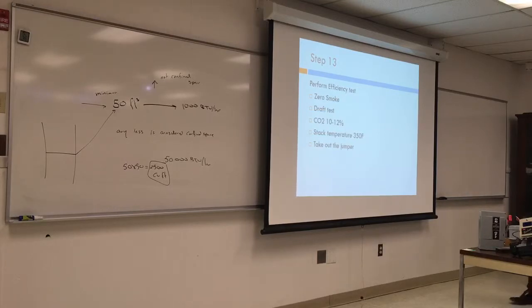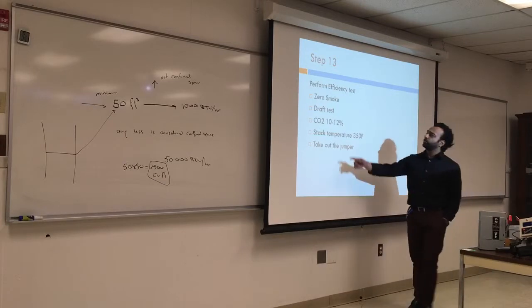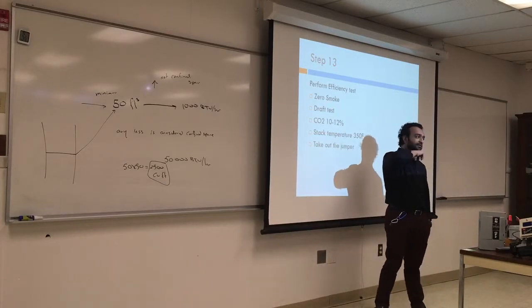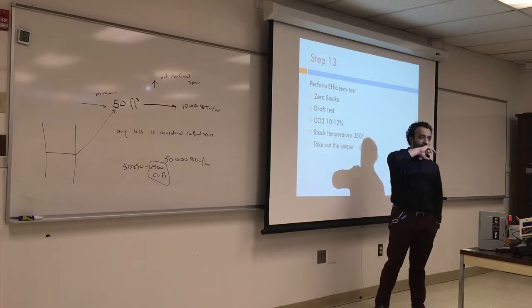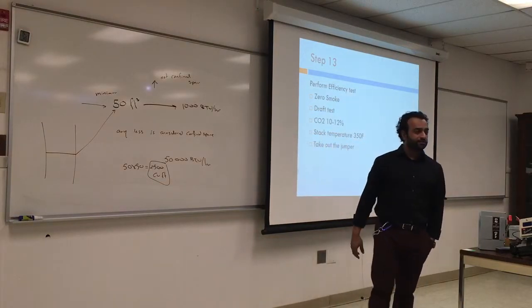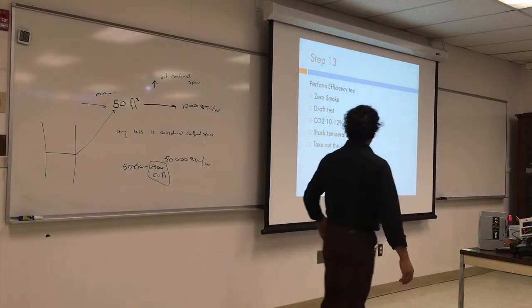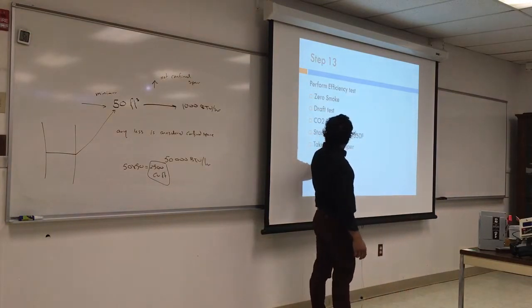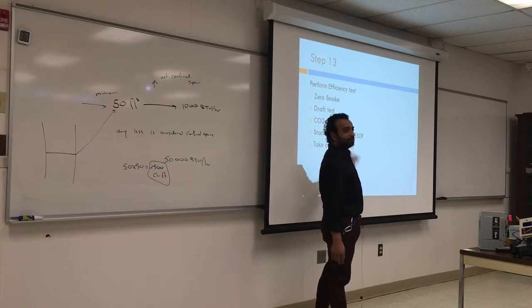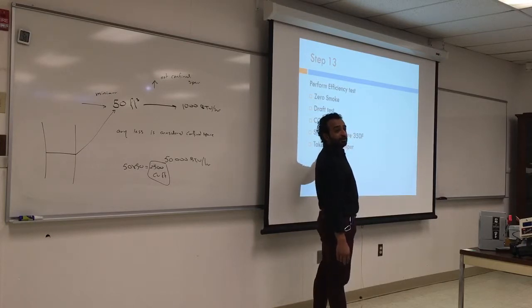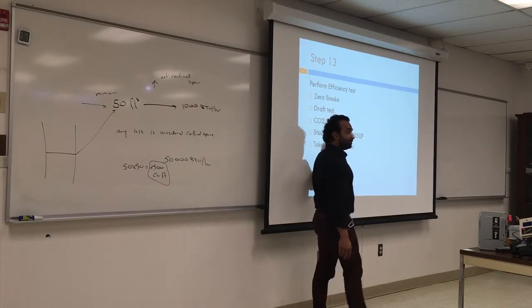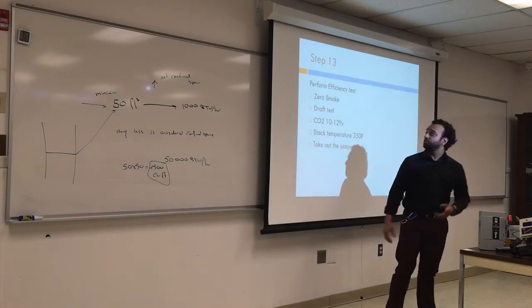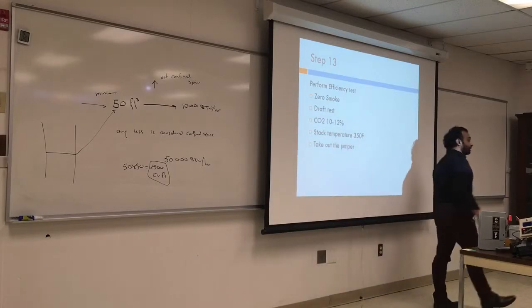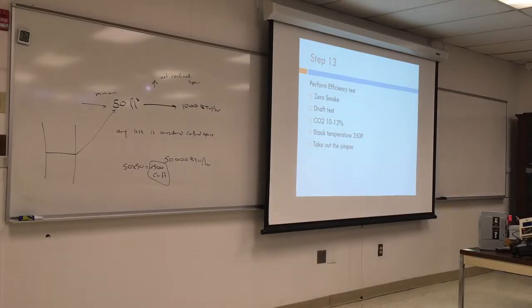If you want to talk a little bit about the CO2 being 10 to 15%, what would the oxygen be? If the air is 20% oxygen and you have produced 10% CO2, you have 10% left, so you consume 10% oxygen. So you can do a combustion test using either an oxygen tester or CO2 testing.